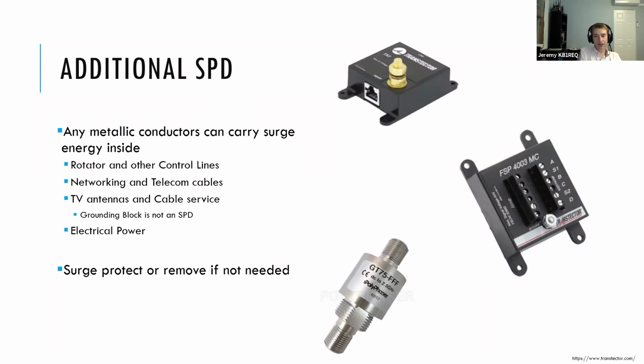We focus obviously on antennas and towers because those are what's sticking up in the air. Those are what, arguably, are going to attract a strike or a surge. But any metallic conductor can carry energy from a surge inside. And so we want to make sure that we are protecting everything else that's coming in to our shack, into our building from outside.